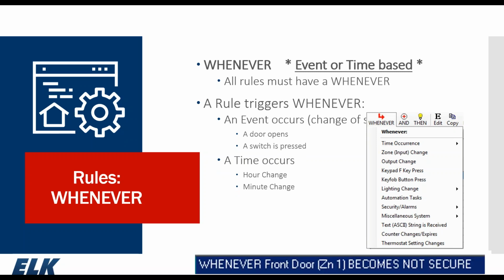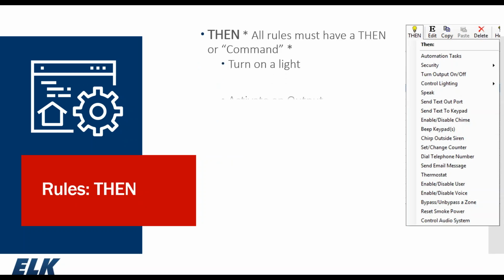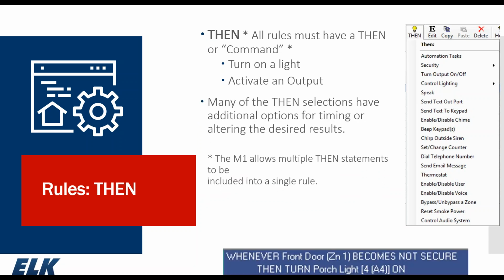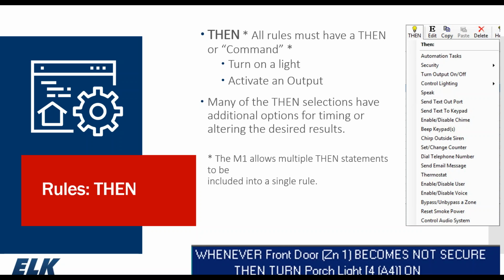Like I said, we can have it based upon zones changing state, a switch is pressed, an hourly change, a minute change, even down to a 1 second change. So in this case, whenever the front door becomes not secure, we have our then, or our action, or our command. We can turn on a light, turn on an output, speak a message, dial a phone number, send an email if you have the XEP module. You can have multiple then statements within the same rule. So each one of them would fire one after the other. So in this case, whenever the front door becomes not secure, turn the front porch light on.